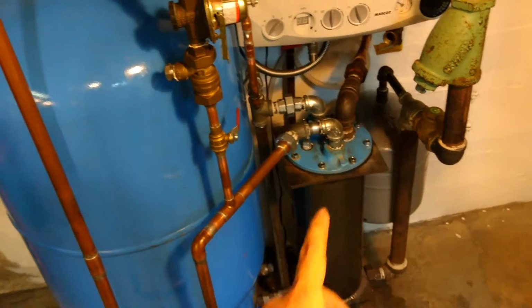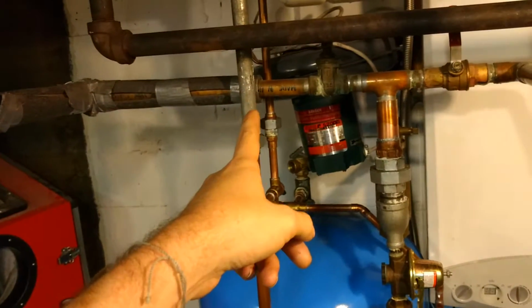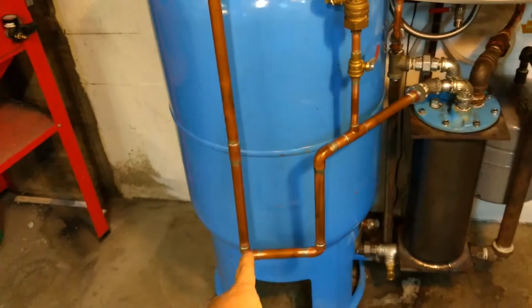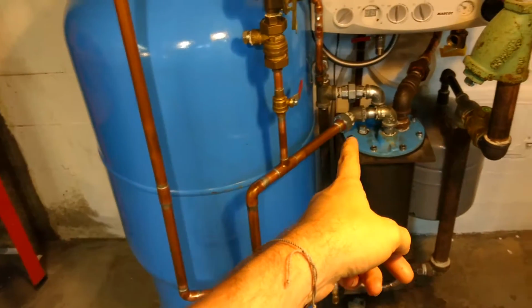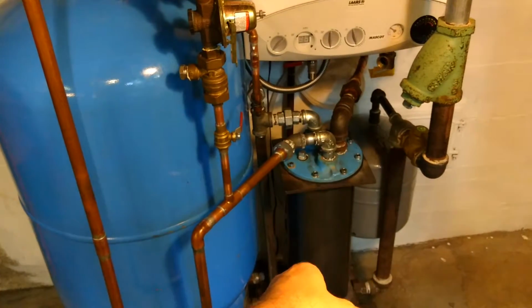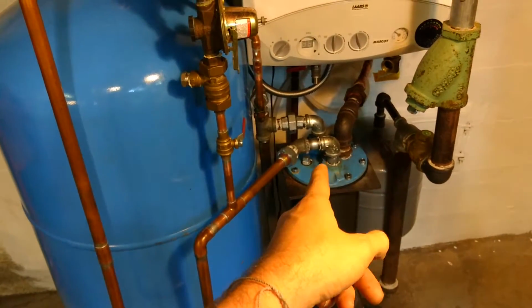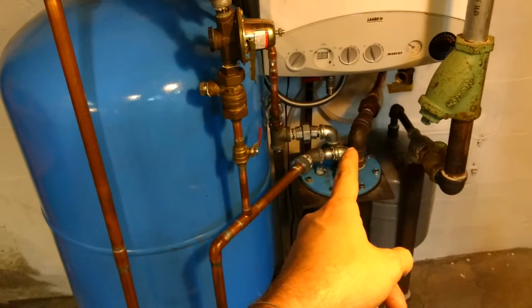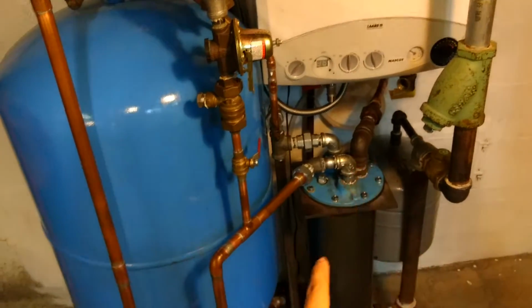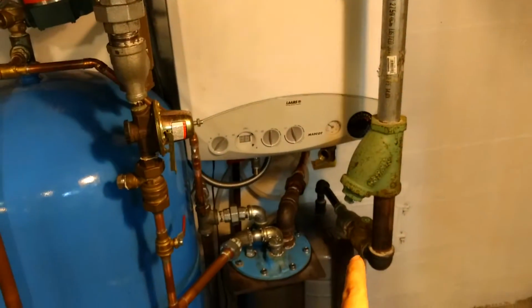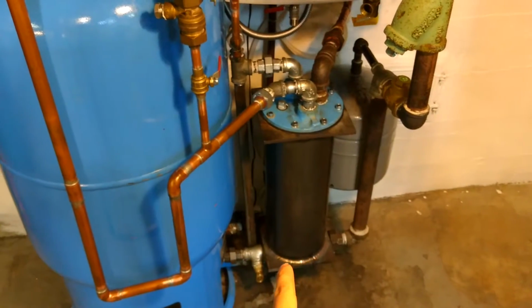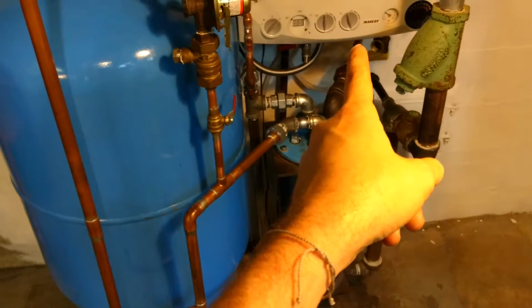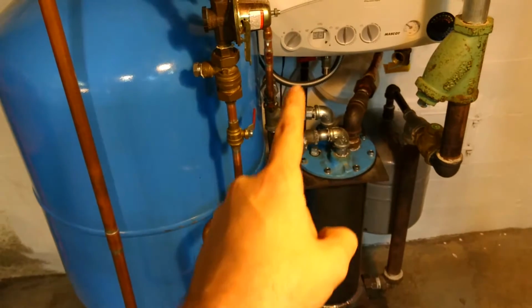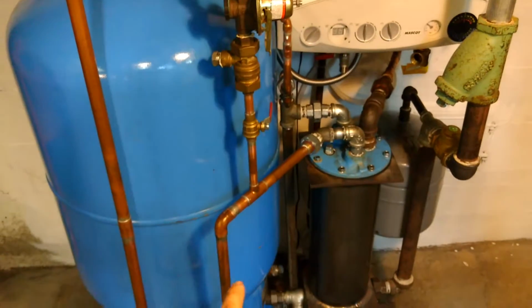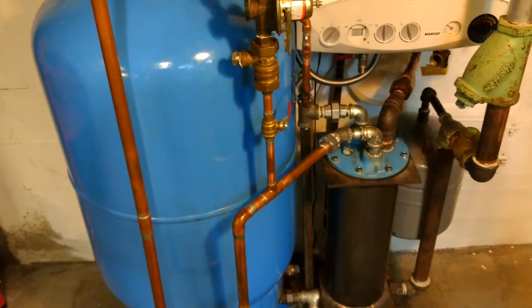So I took the heat exchanger out of that other one, and I made basically a secondary heat exchanger out of it. So immediately from the city, it's galvanized here, the cold water comes down through a heat trap and into this heat exchanger that's surrounded by boiler water. So whenever the house is calling for heat, the water will come from the house return down this path, down to the bottom, up through this tank and into there.